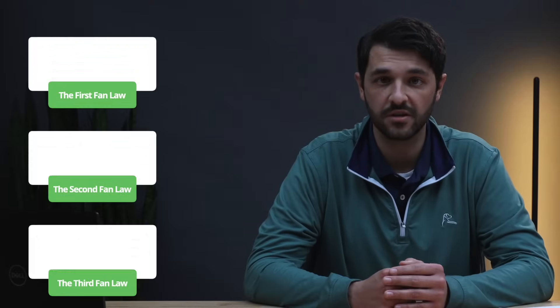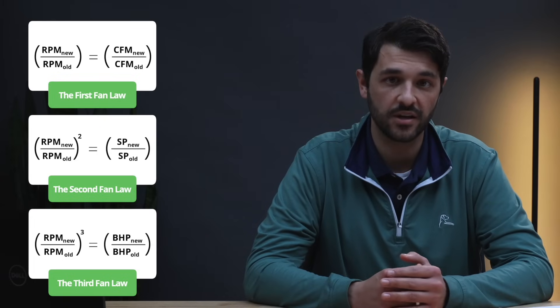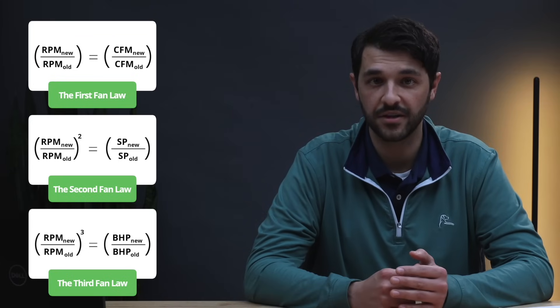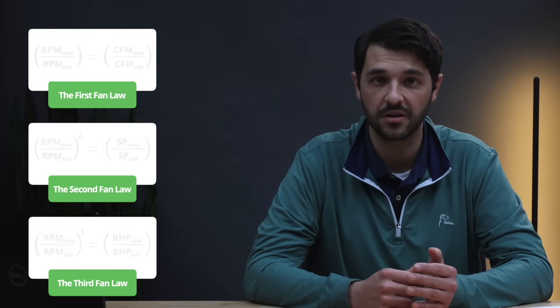To summarize these three fan laws: flow changes proportionately to speed; static pressure changes as a function of the change in speed squared; and brake horsepower changes as a function of the change in speed cubed. There are other fan laws, but these three fundamentals can help you quickly estimate the performance effects of changing speed, either during fan selection or making changes in the field. Thanks so much for watching. In the next video of our Fan Fundamentals mini-series, we'll be reviewing fan performance curves, so be sure to subscribe to our YouTube channel so you don't miss out on future topics.